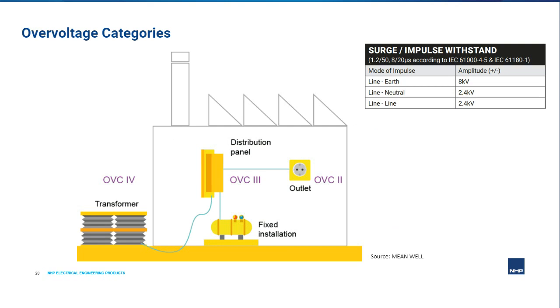As mentioned in the previous slide, I wanted to speak about overvoltage categories as it's an important consideration to make, not only when selecting and installing the REMLIVE unit, but also generally other electrical equipment. Equipment that is installed and wired to high voltage supplies needs to have a suitable overvoltage withstand capability and in accordance to IEC specifications. Overvoltage transients on power lines can cause damage to connected equipment and as a result can also expose users to damage.